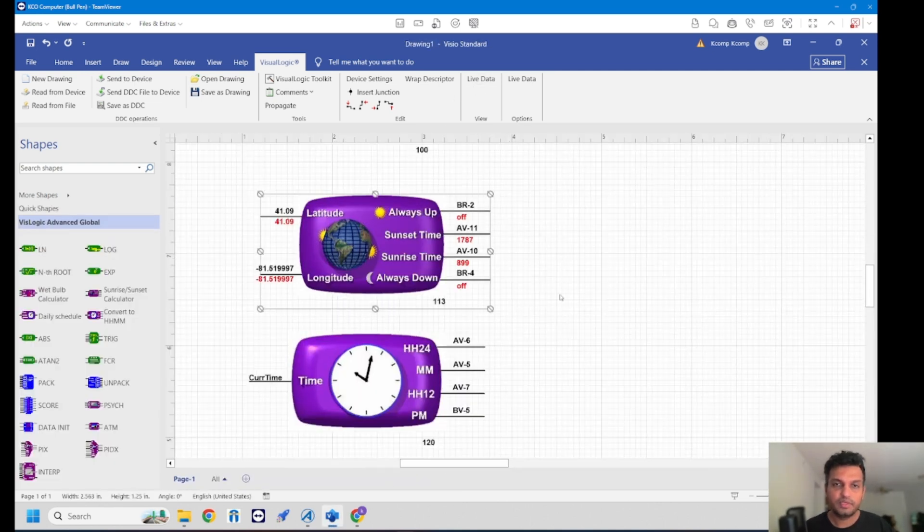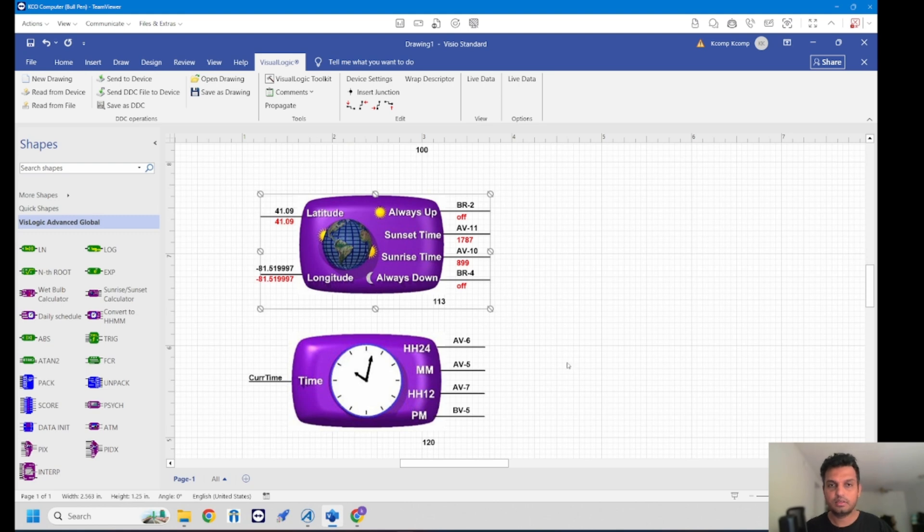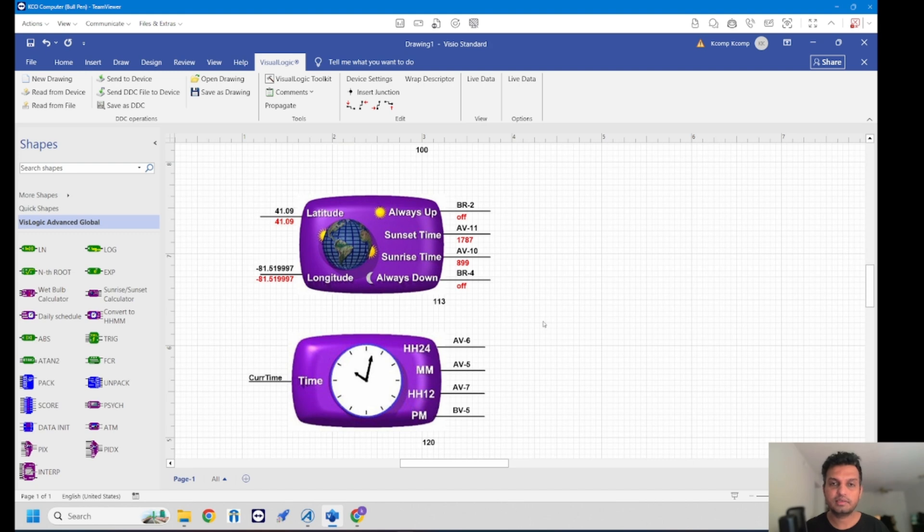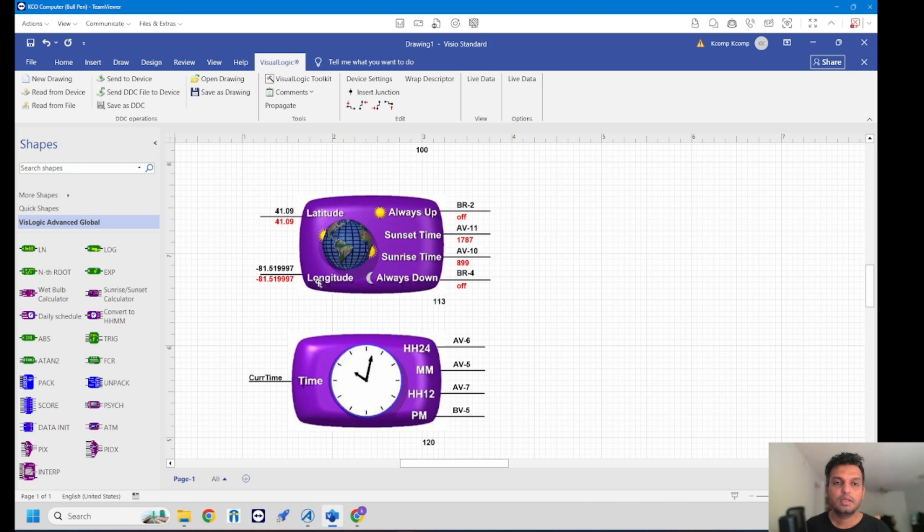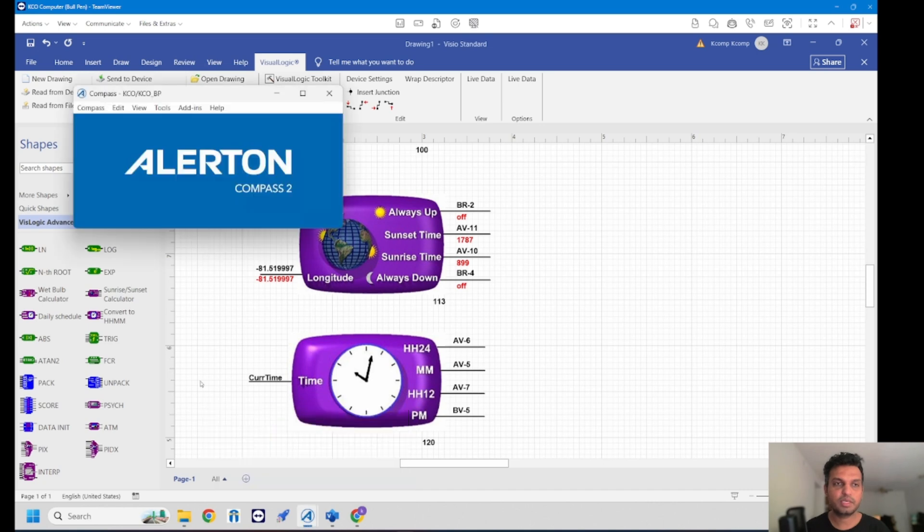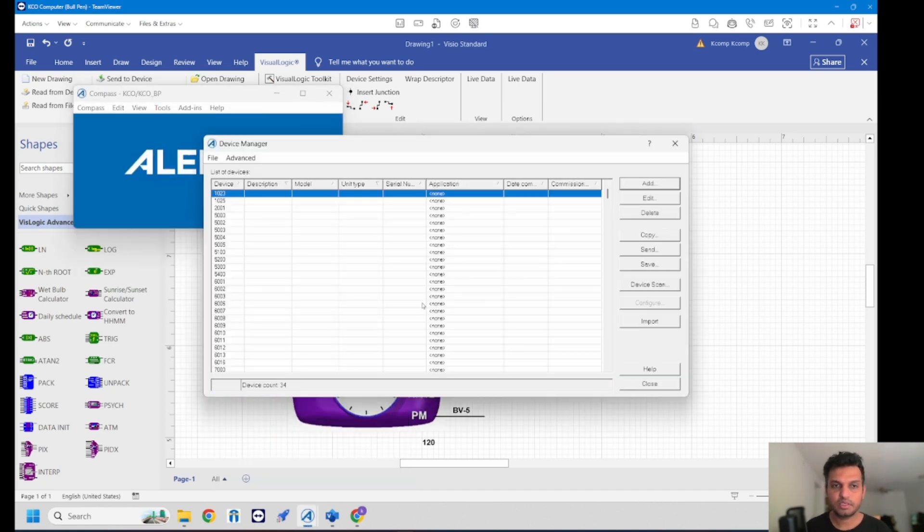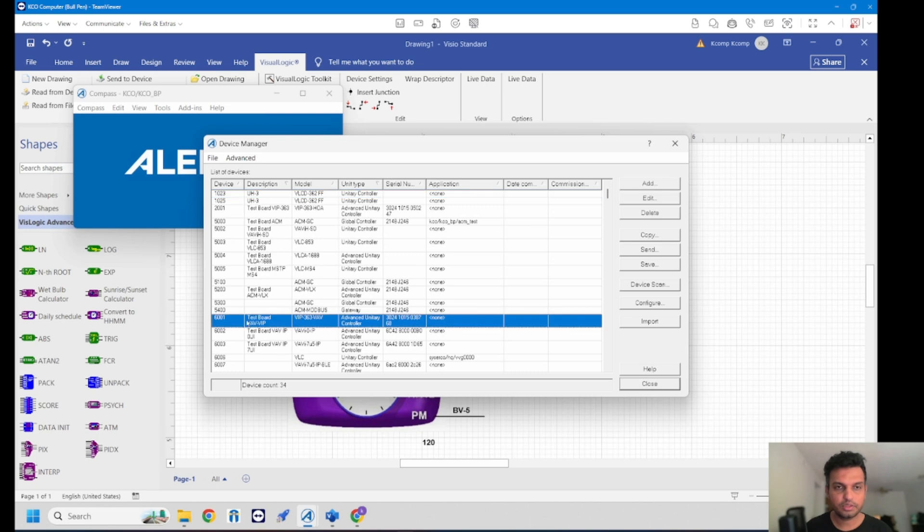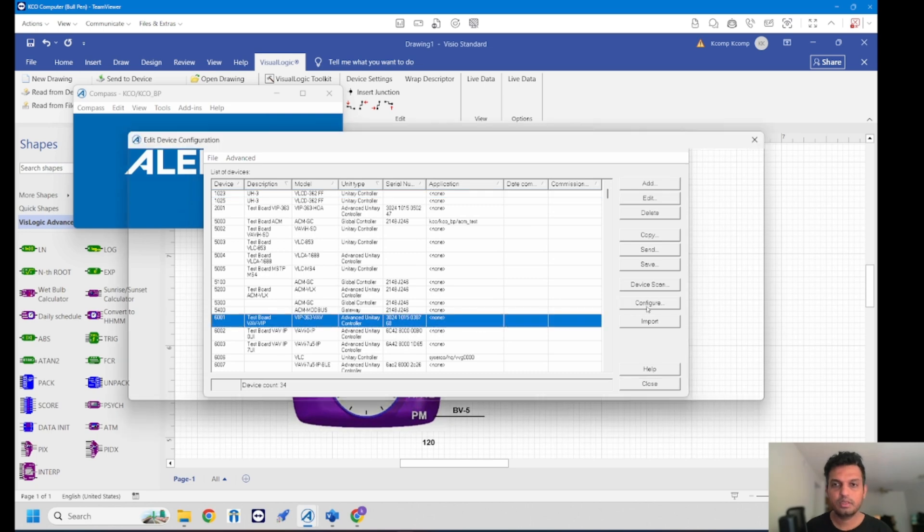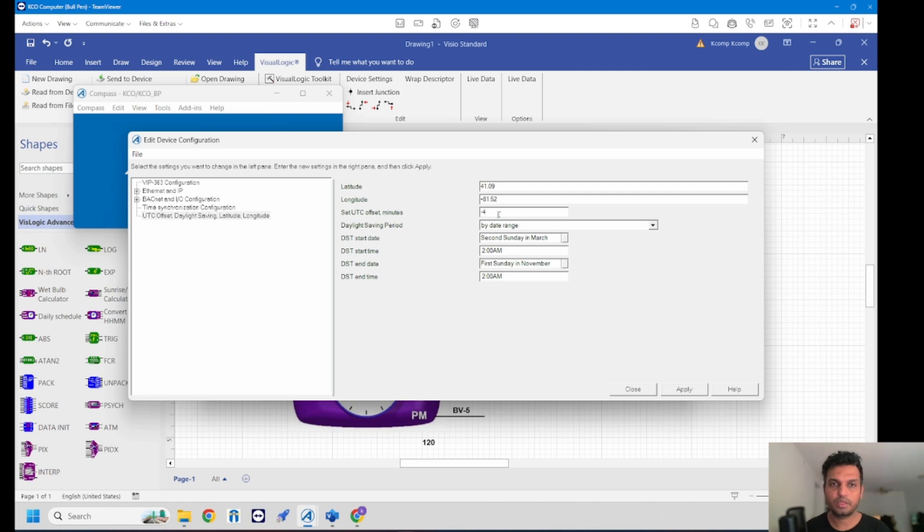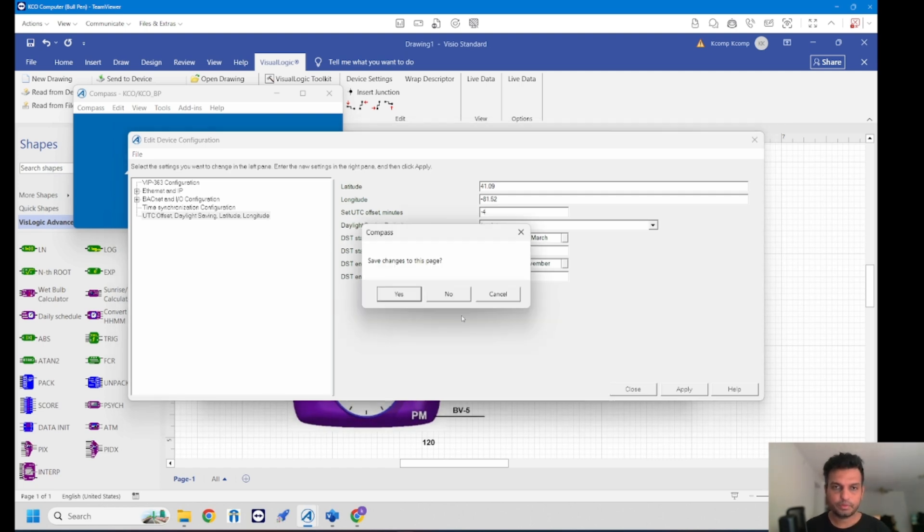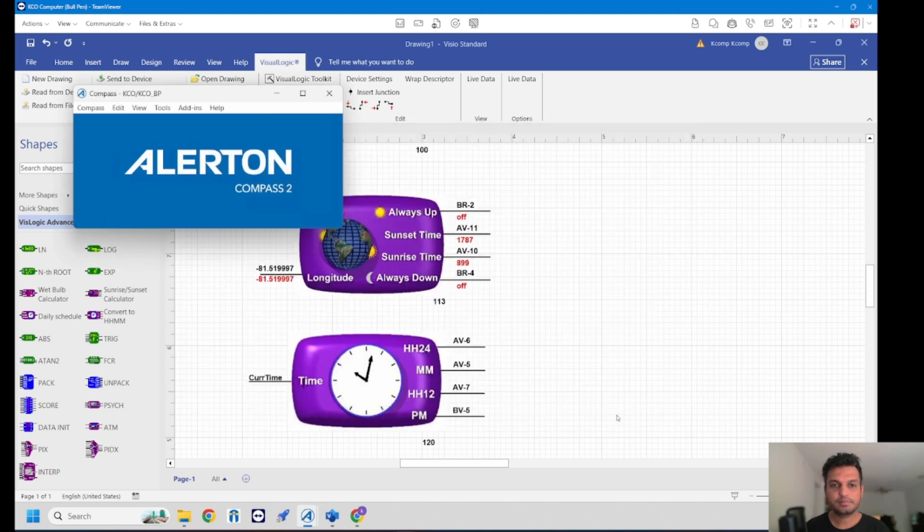We can see here currently the sunset value is around 1787 and sunrise time is around 899. If you are not seeing these outputs that means your latitude and longitude are not correctly set on the controller. That can be seen by going into your device manager, going into Compass device manager and selecting that particular controller. Configuration, the last option that you see here will give you latitude, longitude and also the UTC offset.